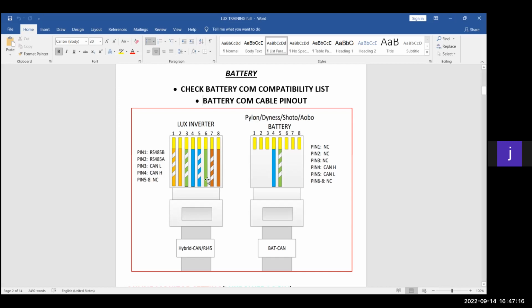The older Luxpower SNA 5000 used a pin configuration where pin 3 of the inverter went to pin 5 of the battery and 4 stayed on 4. Now, with the newer machines that are coming in, we won't have to worry about this anymore. We will only have a straight communication cable that will work between the inverter and the battery, and 99% of the batteries come with a straight comms cable in the box. So this is a big improvement that we are very excited about.